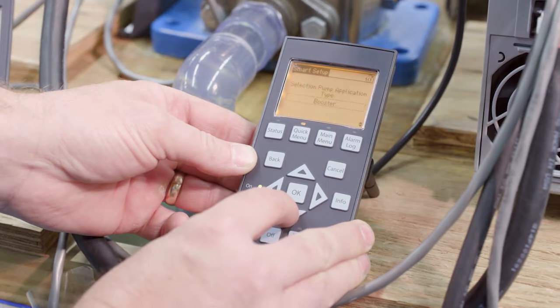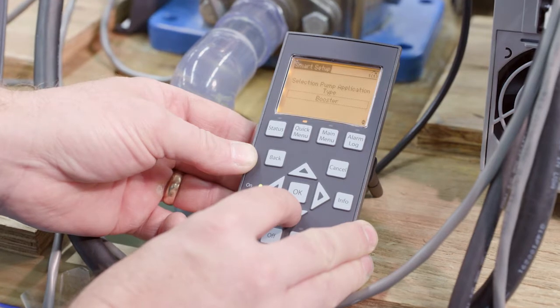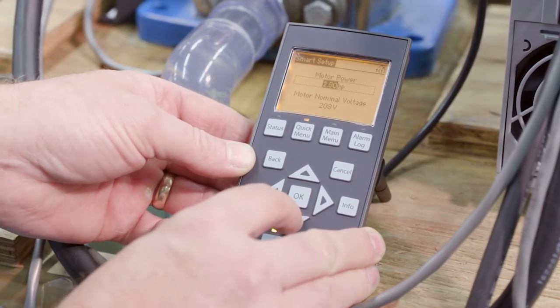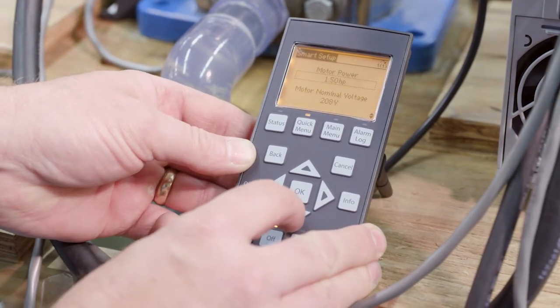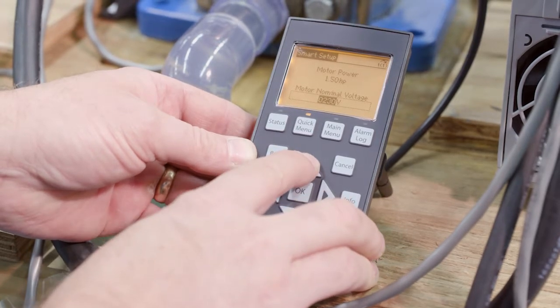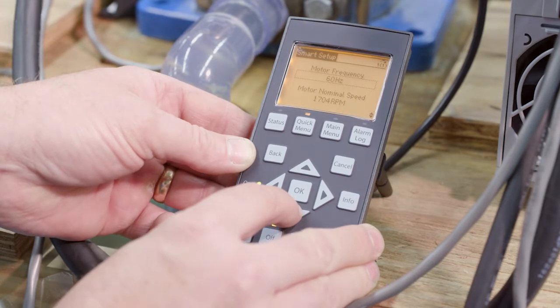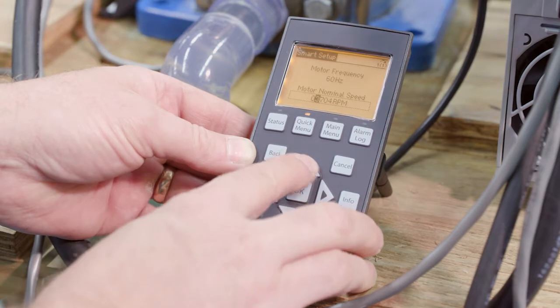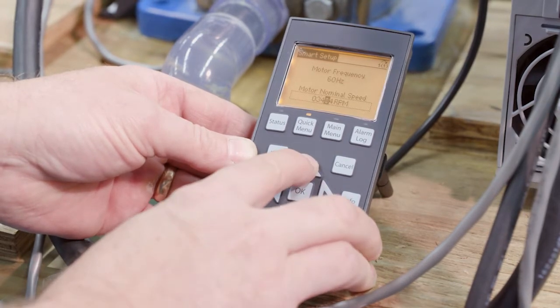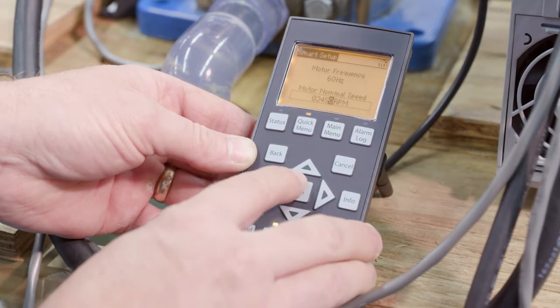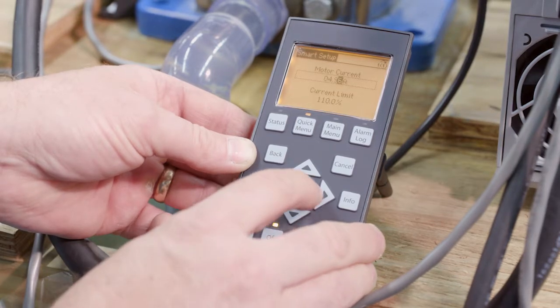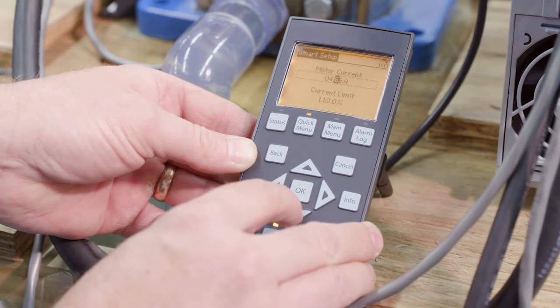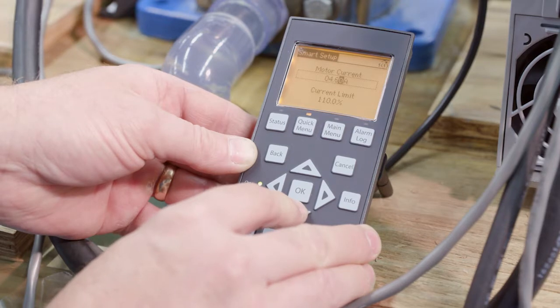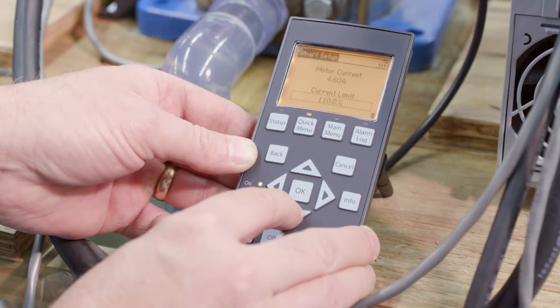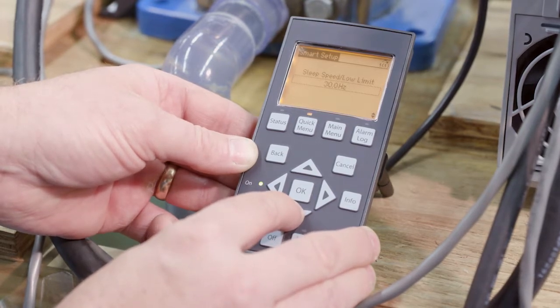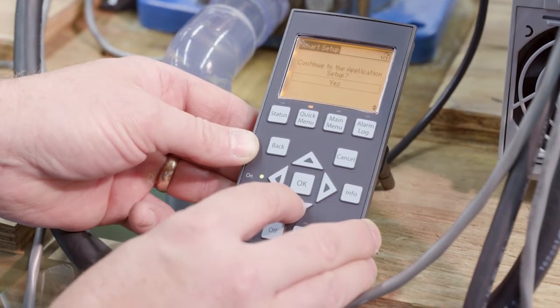And you'll notice that it's the same system, so there's a lot of duplication here. So we got to make the same changes because we have the exact duplicate pump here. So 1.5 horse, 208 volt, frequency 60, speed 3450. Again, same current, which is 4.6. Current limit's the same, right? Service factor amps divided by nominal amps. Surface motor, sleep speed of 30, no filter, continue application setup, yes.